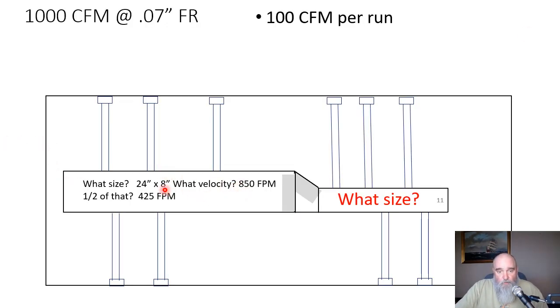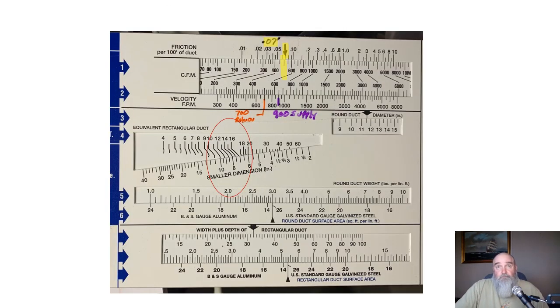So we got 24 by 8 duct, we were at 850 feet per minute moving through it. Half of that was 425. We knew after five branch runs it was time to reduce. So what size is the trunk that's going to carry our remaining five branch runs? Pretty simple. We line the 500 CFM up under my 0.07 friction rate that we calculated using the friction rate worksheet.